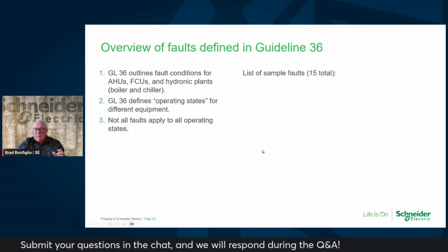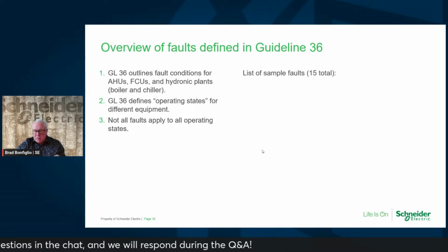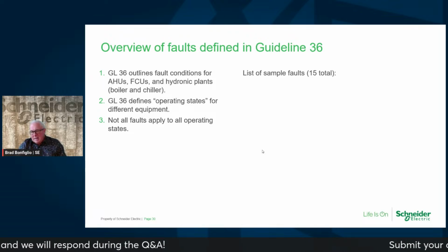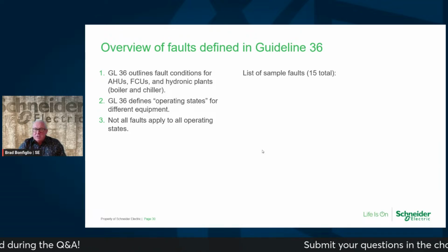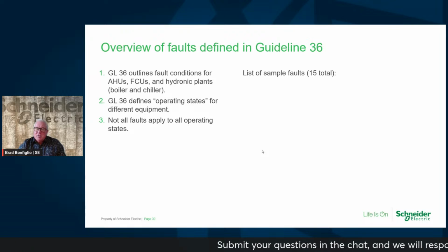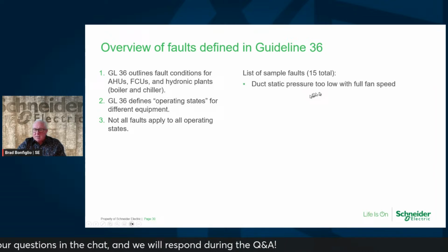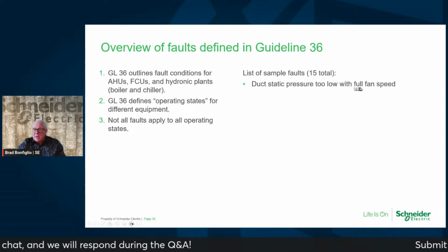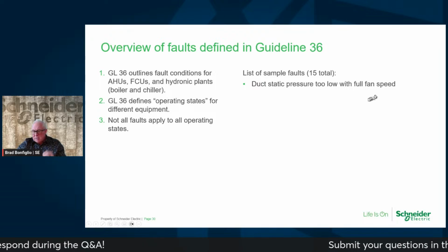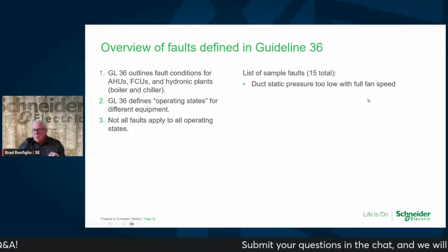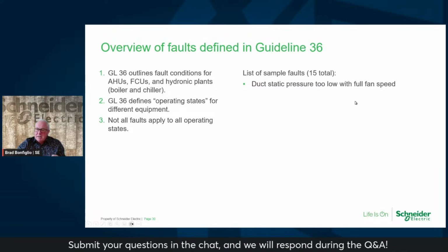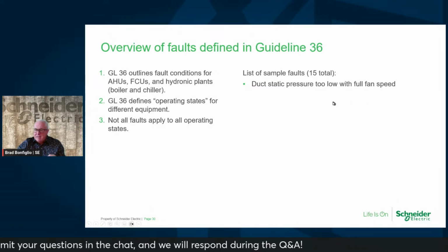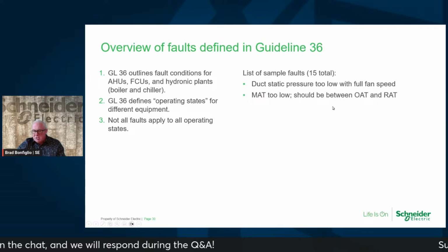There are 15 faults that are defined. So when I say that, the guideline is set up in sequence, so that the entire sequence of operation actually defines these faults, and there's 15 of them. And let me give you an example of some of these. Duct static pressure is too low when the fan is in full speed. So this gets beyond just, oh, it's meeting set point, not meeting set point, or it's meeting set point, but yet we're wasting energy. This gets above and beyond that. This is the faults of where we're seeing the issues.